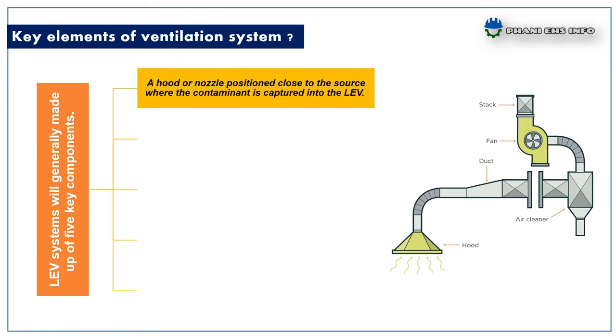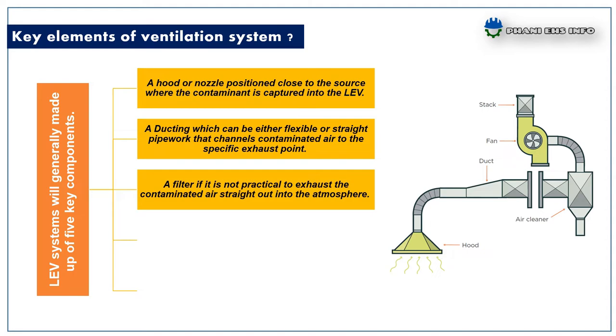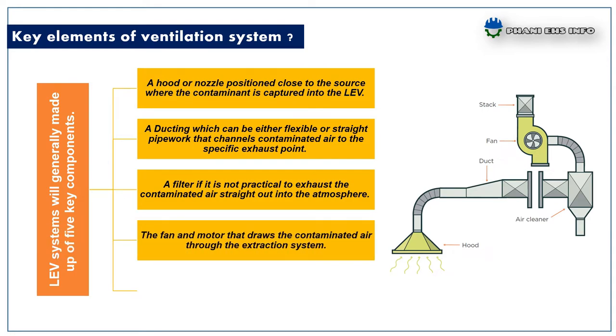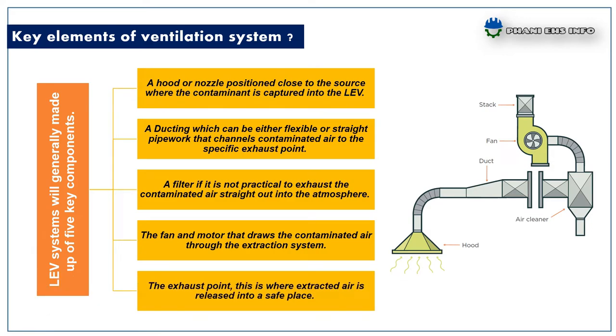Next, the key elements of a ventilation system. A local exhaust ventilation system will generally be made up of five key components. First, a hood or nozzle positioned close to the source where the contaminant is captured into the LEV. Second, ducting — either flexible or rigid pipework — that channels the contaminated air to the exhaust point. Third, a filter, if it is not practical to exhaust contaminated air directly into the atmosphere. Fourth, the fan and motor that draws the contaminated air through the extraction system. Finally, the exhaust point, where extracted air is released into a safe place.